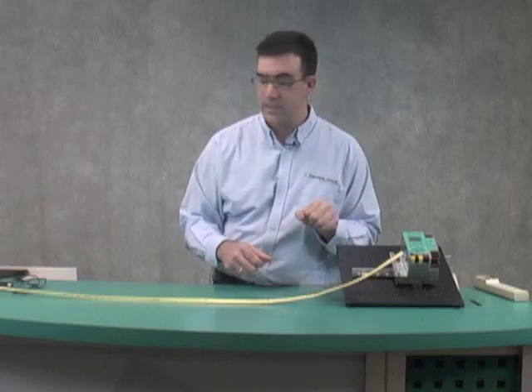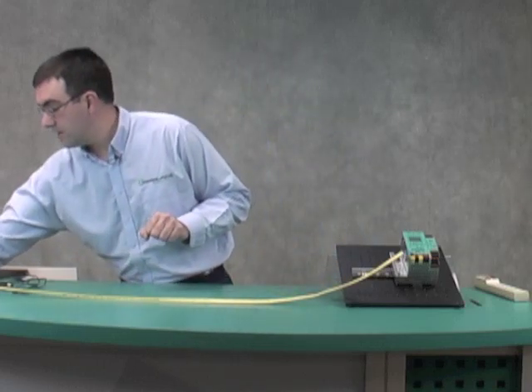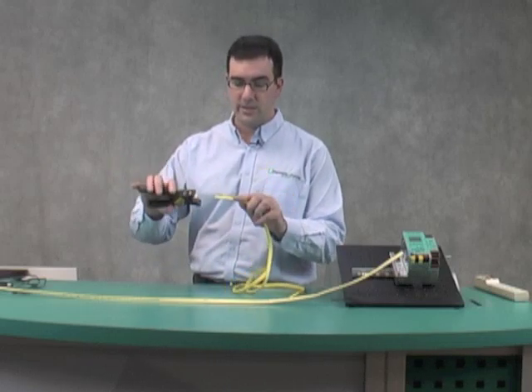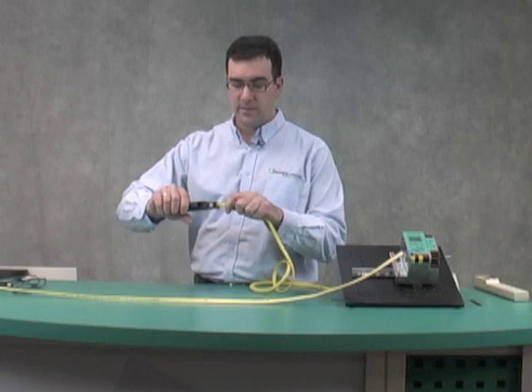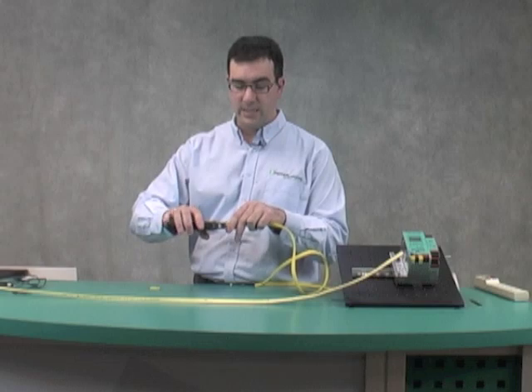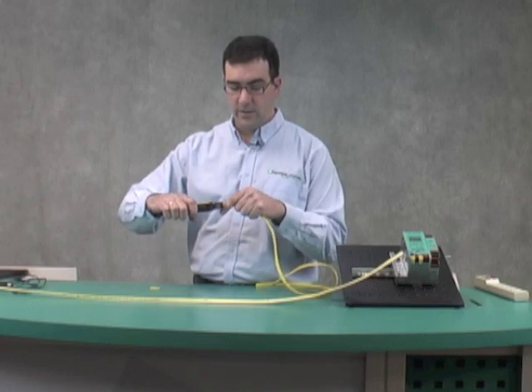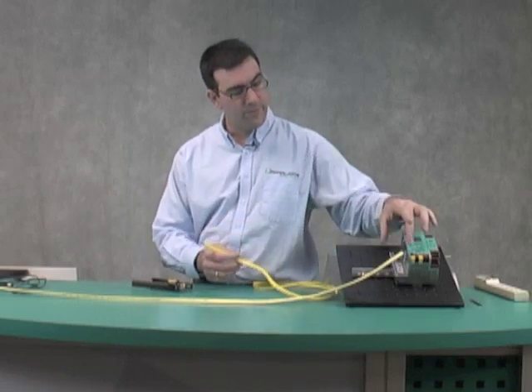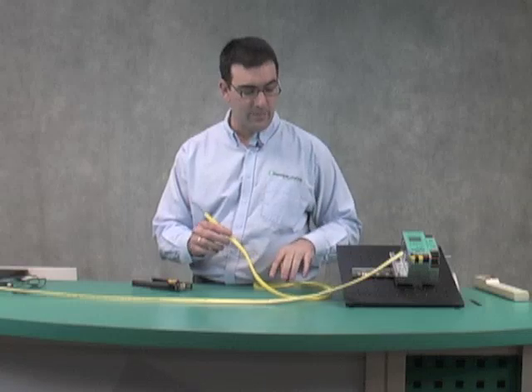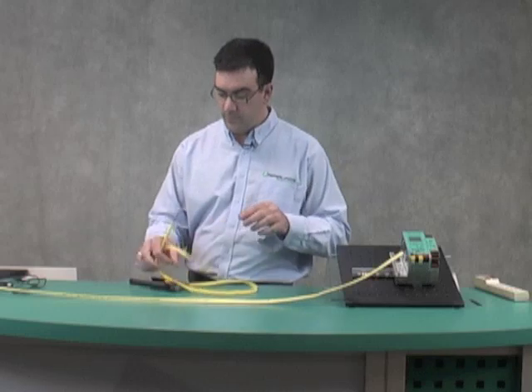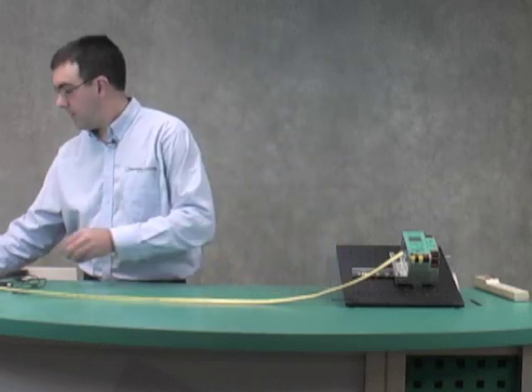The flat cable here was easily stripped. I want to show you that with our stripping tool. You can see I use this here. It really makes it easy when you want to strip your flat cable. I usually strip about one inch at a time and then I'll take off maybe two inches, strip it back, and then I put ferrules on just to make sure that the copper didn't fray and maybe accidentally short out.